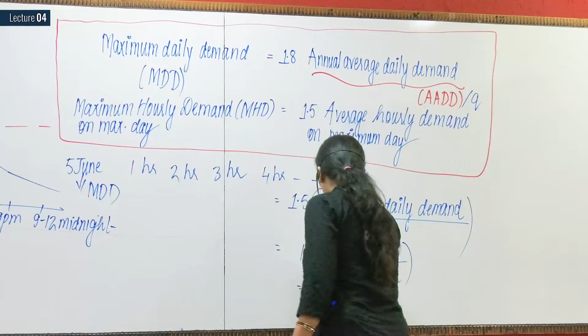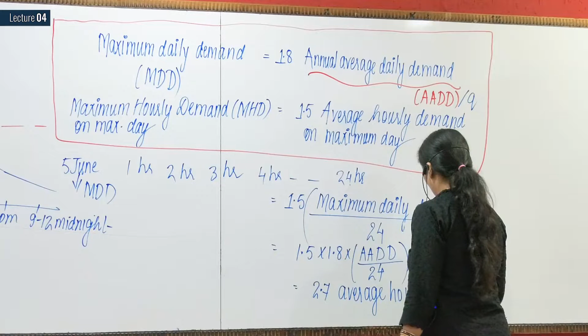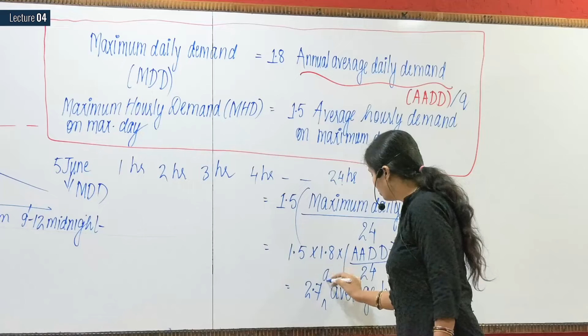So if you solve this, what will you get? 1.5 into 1.8 will give you 2.7, and this annual average daily demand divided by 24 will give you average hourly demand. Clear? So you can say that 2.7 times annual average hourly demand. So you got two relations. One thing is, if somebody asks you, maximum daily demand, if you want to calculate, it will be 1.8 times annual average daily demand. Annual average daily demand, I have already explained to you initially.